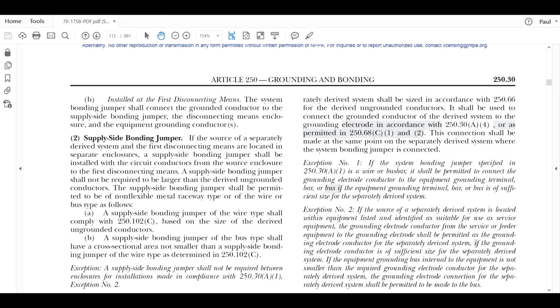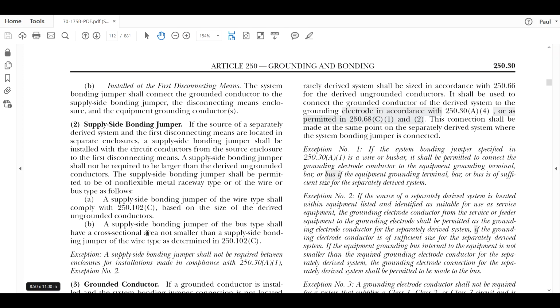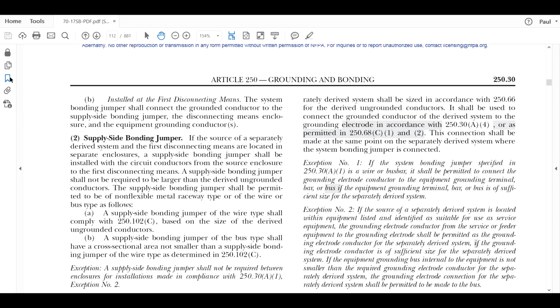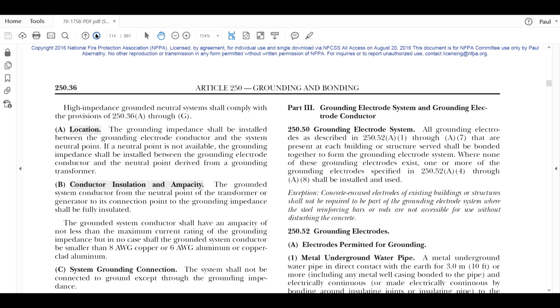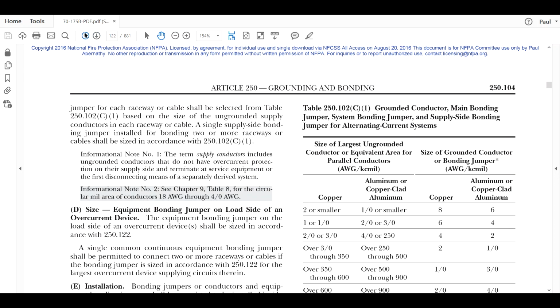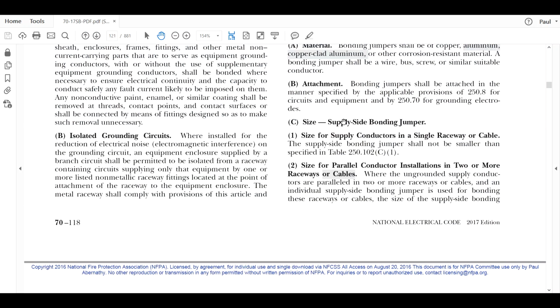So let's go back to the code. We're going to size it based on 250.102(C), so we're going to jump around a little bit. I'll just jump down to it because it won't take but a second. There we go, right there. It says based on C. Now, C says supply side bonding jumpers. In our case, we have only one single raceway, made up of EMT and FMC. It says the supply side bonding jumper shall not be smaller than specified in the table. So we're going to go to Table 250.102(C)(1). That's what we're going to deal with.